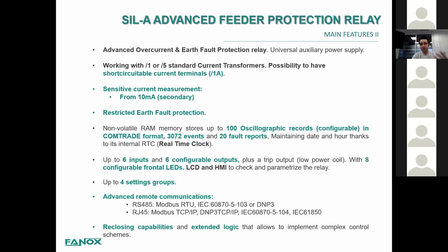We also have 4 settings groups available, and the biggest improvement, or the biggest difference of this relay in relation with the self-power relay, is that we have advanced remote communications. It can be an RS485 port with Modbus, IEC, or DNP3, but we also have TCP features through Modbus, DNP3, IEC 104, or IEC 61850.